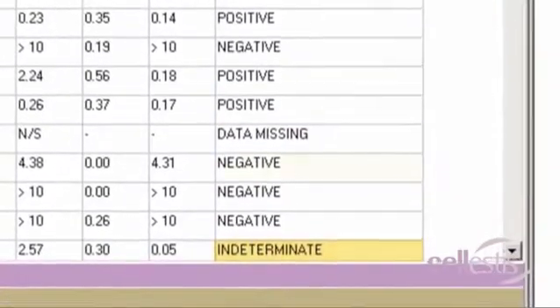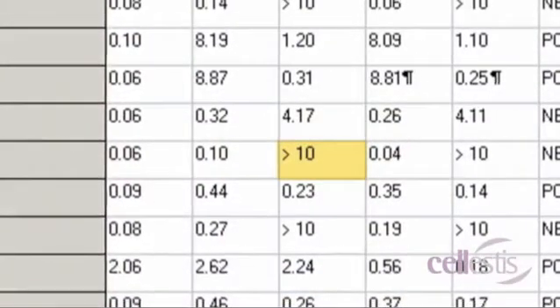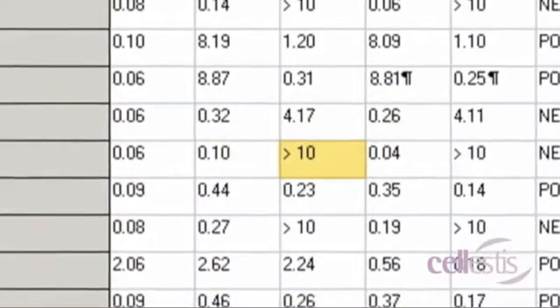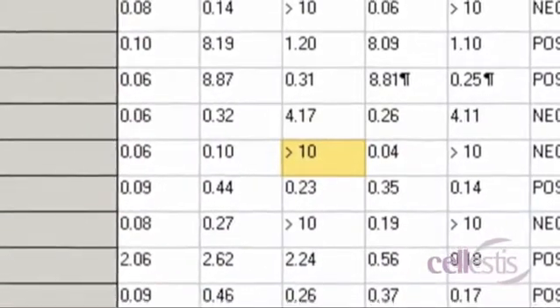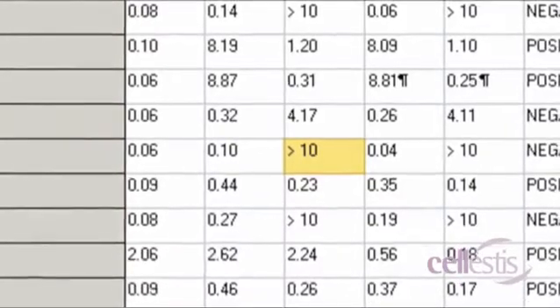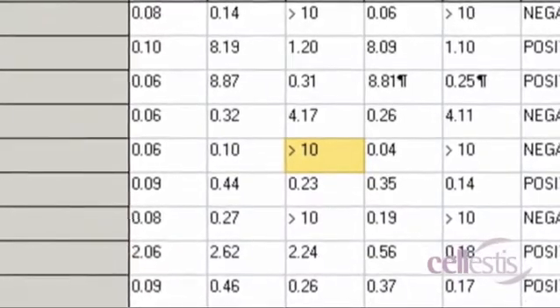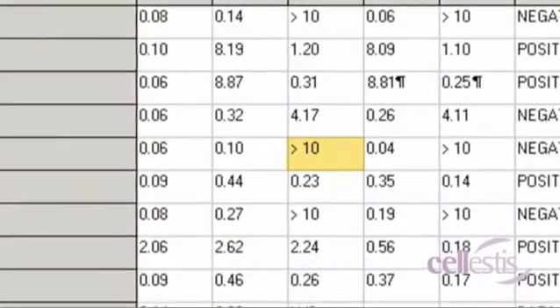All concentrations greater than 10 international units per milliliter are reported as greater than 10, as such values fall beyond the validated linear range of the ELISA.